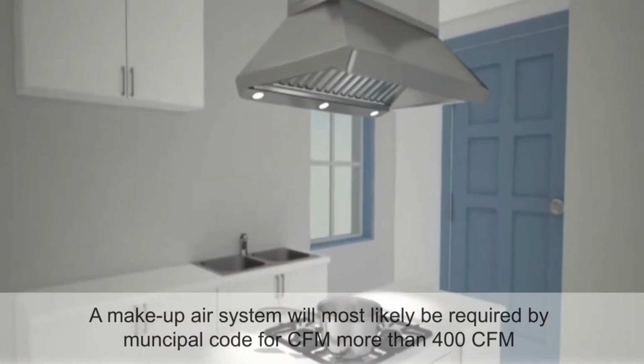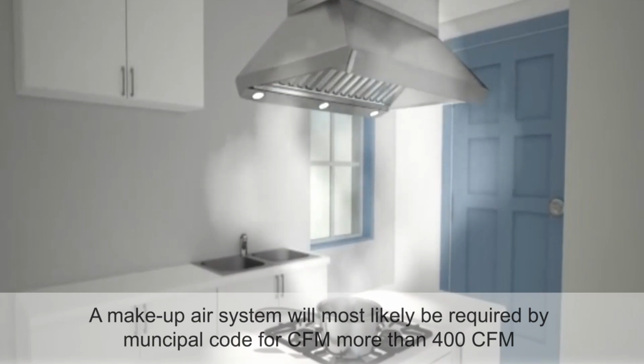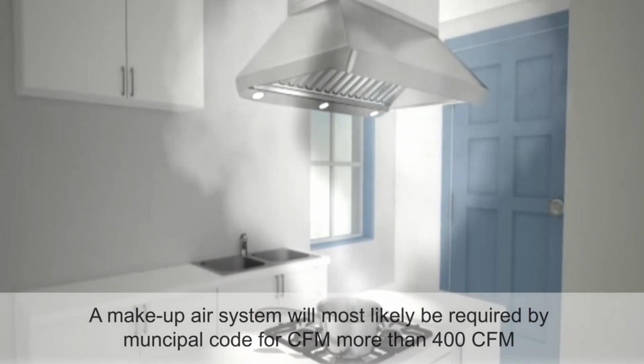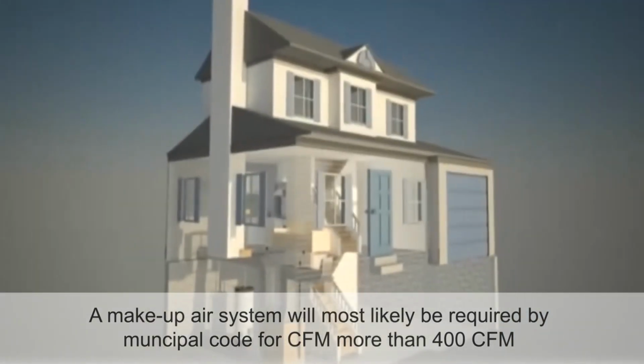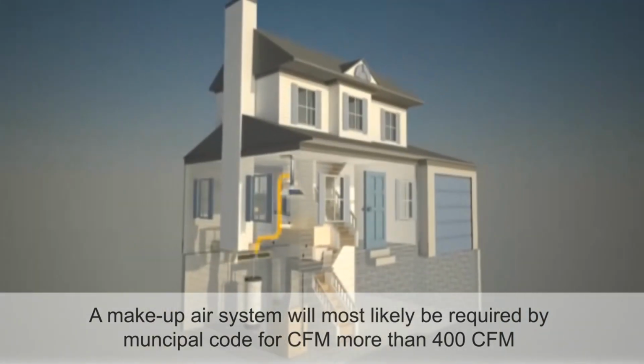Range hood performance can also be negatively affected when there is an inadequate source of outside air. As a result, range hoods that operate over 400 CFM may cause home depressurization and operate at a reduced performance, allowing smoke and odors to linger in the home. International Residential Code requires that homes with range hoods over 400 CFM have a makeup air system.